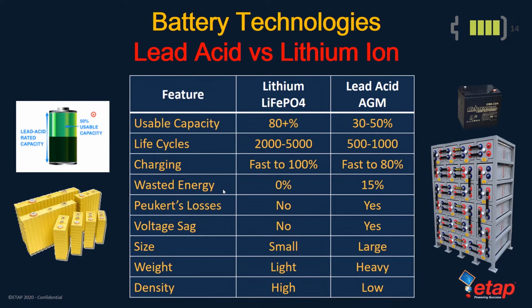It is typically considered wise to use just 30 to 50% of the rated capacity of lead acid deep cycle batteries. This means that a 600 amp hour battery bank in practice only provides at best 300 amp hours of real capacity. Even if you're going easy on your batteries and are careful to never overly drain them, even the best deep cycle lead acid batteries are typically only good for 500 to 1,000 cycles. If you're frequently tapping into your battery bank and utilizing batteries, this could mean that your batteries may need replacement after less than 2 years of use.